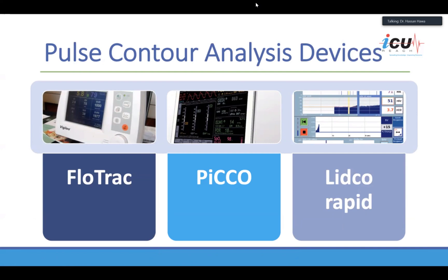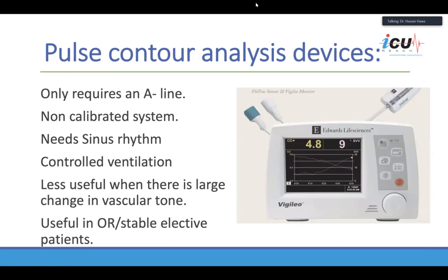Pulse contour analysis devices include FloTrac or Vigileo by Edwards, PiCCO or PiCCO Rapid, and LidcoRapid, which gives you analysis of the pulse contour. You need the A-line and then attach this device to it. The problem with these systems is they are not calibrated — that differentiates them from the full version of PiCCO or Volume View. These devices are ideal for patients in sinus rhythm, passively breathing under controlled mechanical ventilation, and are best for OR or stable elective cases or patients on low doses of pressors in ICU.